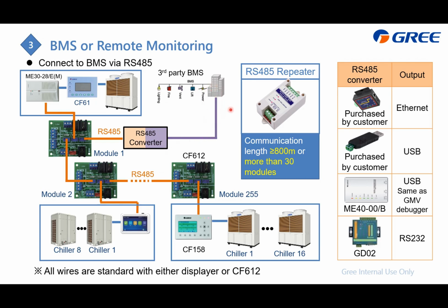On the other hand, for the communication, if the length is more than 800 meters or there are more than 30 modules, which means 30 of this CF612, you need to apply this RS485 repeater to ensure the communication.